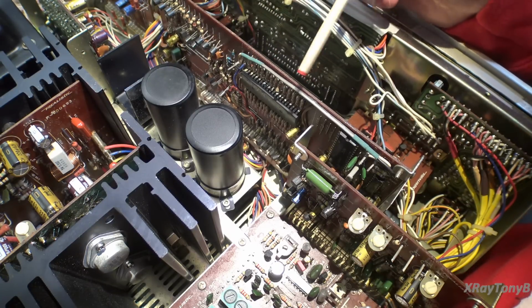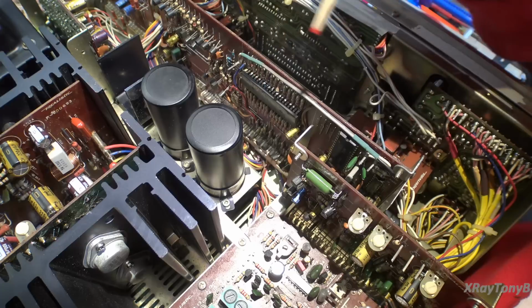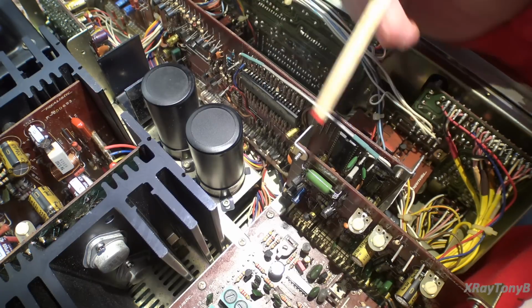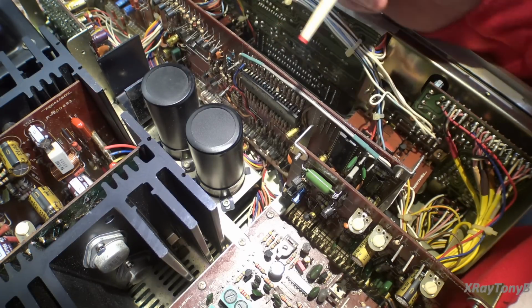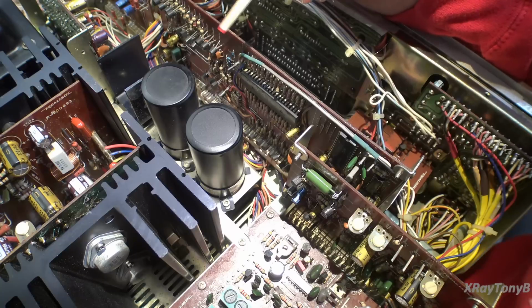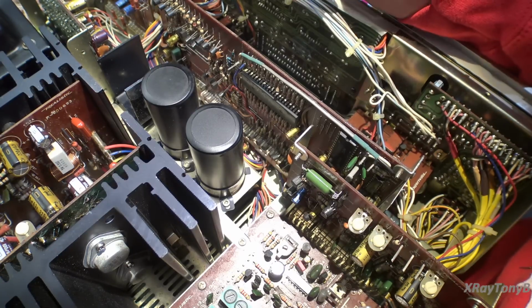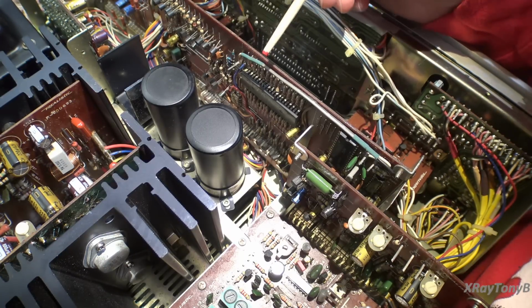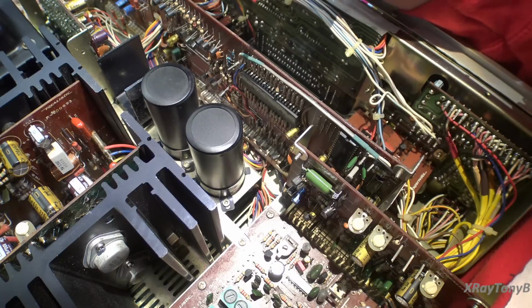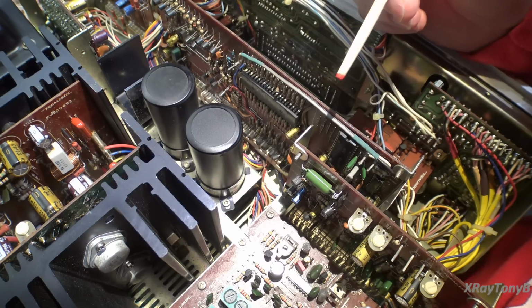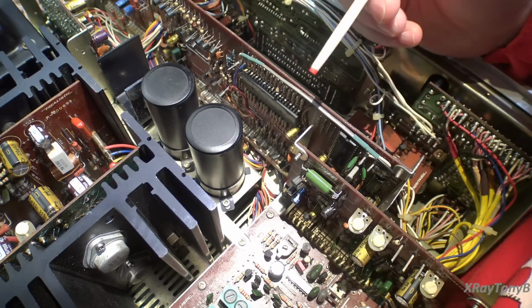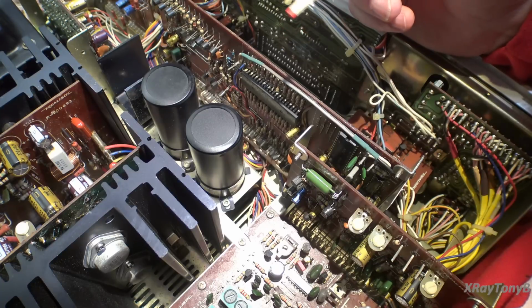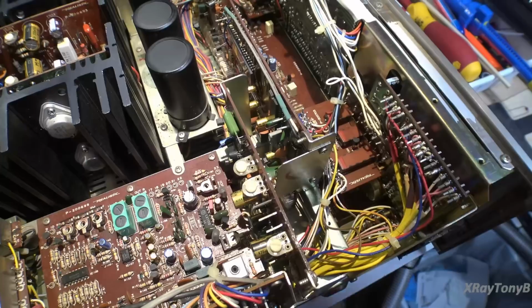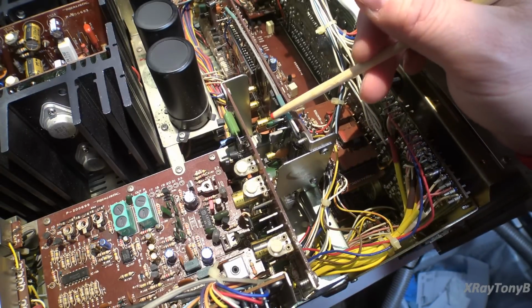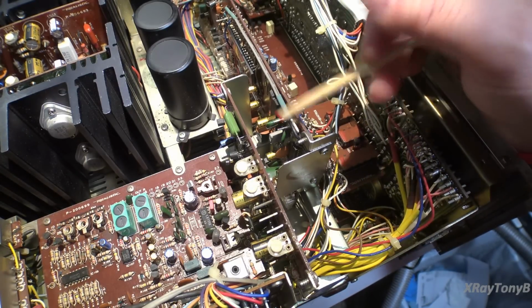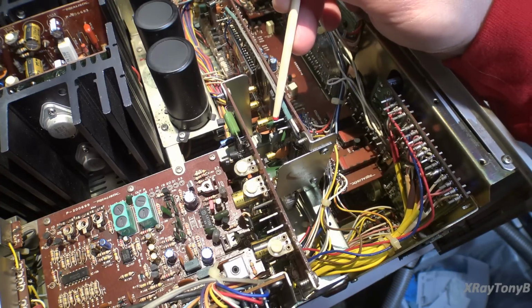megahertz signal, the reference oscillator. And it won't get swamped down because it actually has a little higher output, and it has a capacitor decoupling it from the chip. So we can connect right onto that and measure that 160 kilohertz. And if we get 160 kilohertz, we know that our 10.24 megahertz reference oscillator is working properly. Now the place to measure it is they put these two little convenient posts here, and this is the one where the actual signal is going to be.